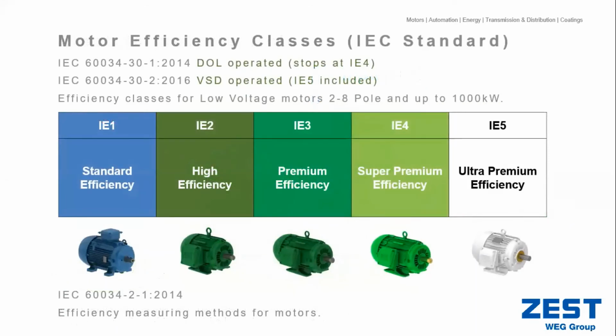According to international standards, there's an IEC directive implemented in 2014 stating all electric motors started direct-online will stop at efficiency class IE4. From 2016, a standard says even motors operated by variable speed drives would include an IE5 level. What does this mean locally? The speed range would be from 2 to 8 pole, covering a wide range of electric motor speeds, up to 1,000 kilowatts, which generally fits most industry applications.